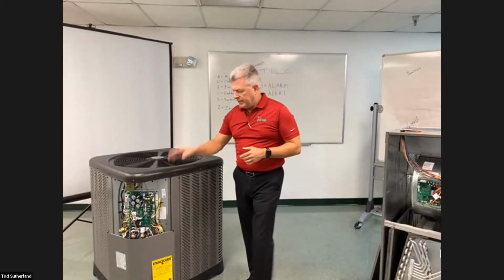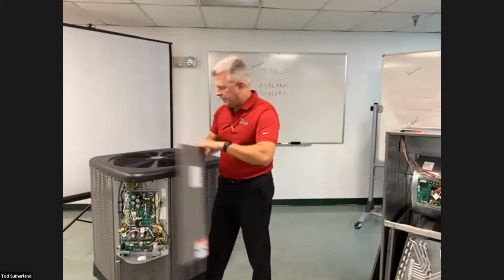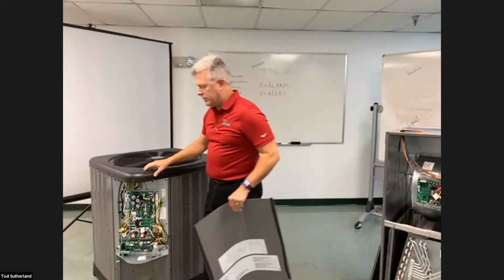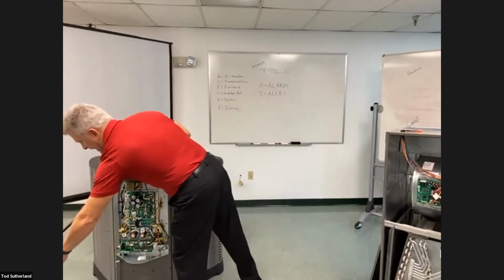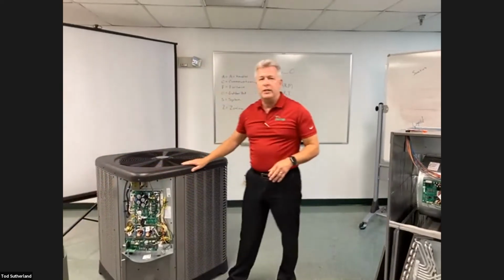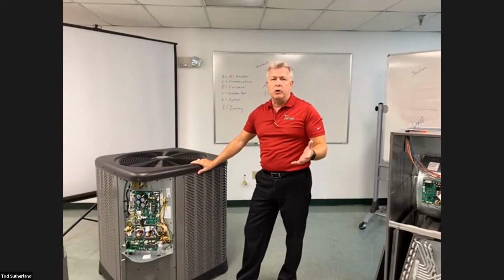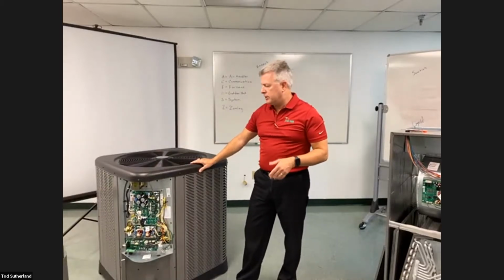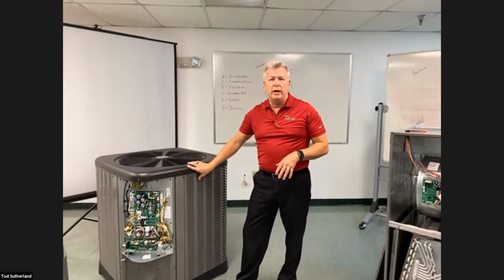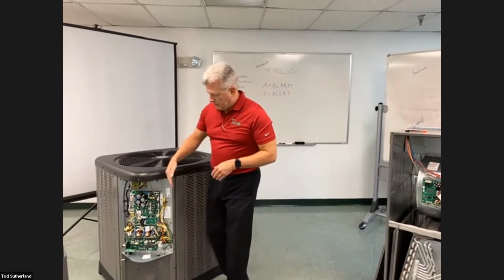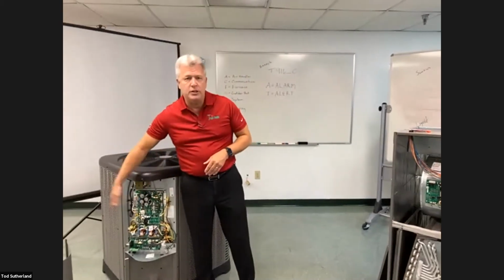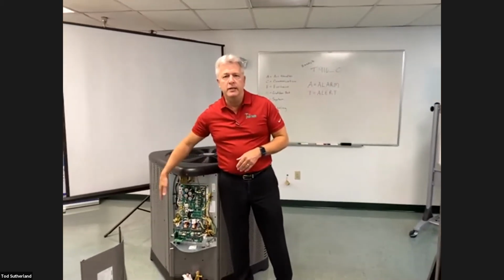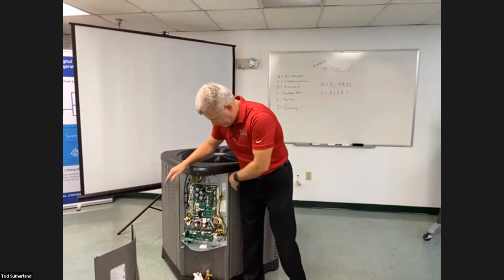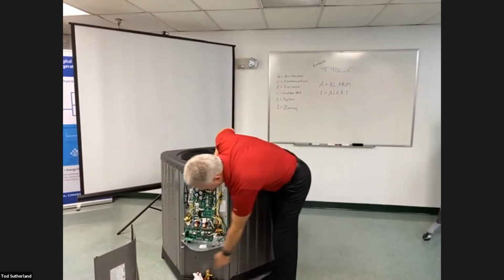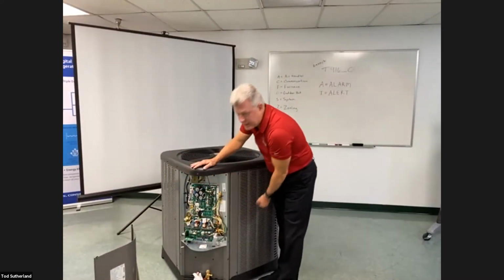So first, I've already taken the cover off of this condensing unit, but I do want to go over some of the features that are inherent to all the Ruud condensing units, even some of the commercial equipment that we're getting into on the splits, all basically have this new body style. We boast that we have one of the largest access panels here in the industry. That's 15 inches wide with a couple of screws right down here. This whole panel lifts and comes out.